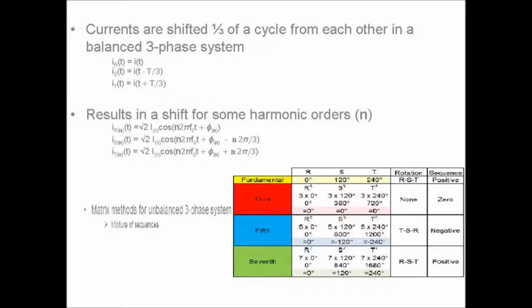You can break things down. So what happens is you've got a negative sequence on the phases for the fifth harmonic. And then the seventh, it works out that it's a positive. So what in essence happens here is you're introducing some sort of torsion onto the system. And if that interacts with, say, a motor or a generator or something like that, it can cause your generator to have to do extra work to overcome this torsion that's happening.